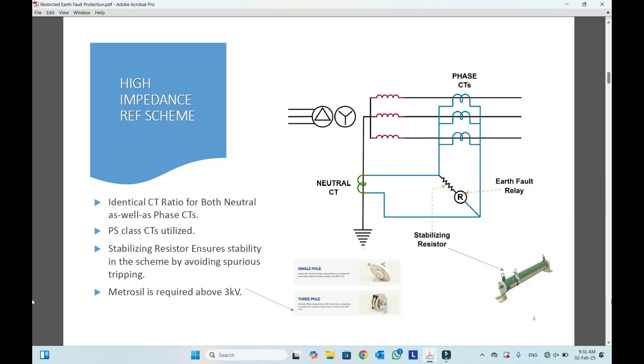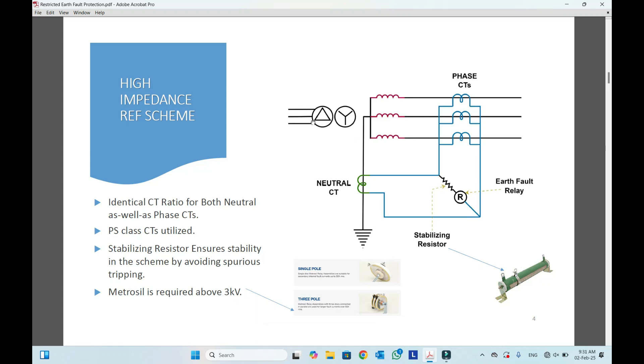As shown in the figure, we have a power transformer with one winding in delta and the other winding in star. The winding which is in star is usually applied for restricted earth fault protection because in the star connection we have the neutral connection available, and we place the neutral CT there. In the high impedance REF scheme, the sum of the phase CTs is combined with the neutral CT as shown in the figure.